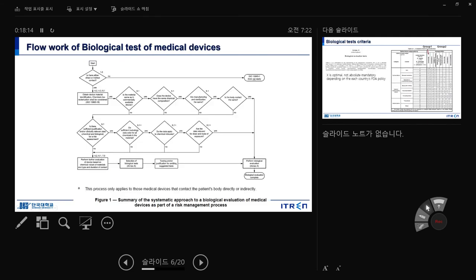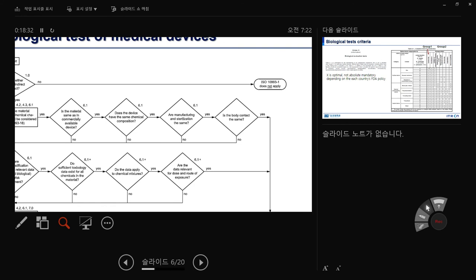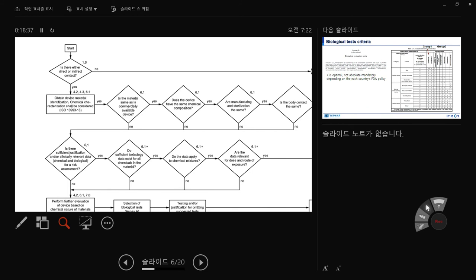This is the basic flow for biological testing of medical devices. First: is your material in direct or indirect contact with the body? If not, you don't need to apply the ISO standard — it's not a biomaterial. If yes, you obtain device material identification, and chemical characterization shall be considered. Which means: whenever you have a new material, the first step is always characterization — chemical, physical, without any cells. You need to know the composition, roughness, color, and degradation behavior.